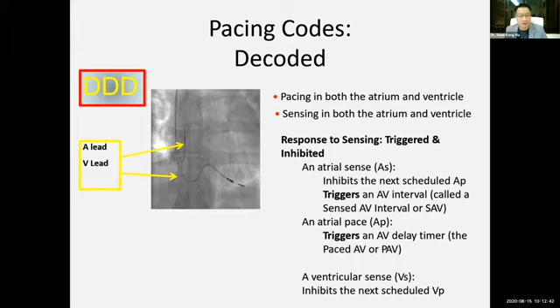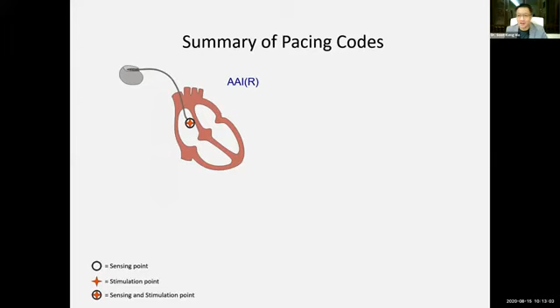Hence, in summary, we have a lot of other pacing codes. You can use the same concept to decode all these different iterations of codes. AAI means pace in the atrium, sense in the atrium, and if you sense an intrinsic activity, you inhibit yourself. VVI, I spoke about earlier on. DDD, I spoke about earlier on, and VDD. Now, VDD is a single lead system, whereby it can sense both the atrium and the ventricle, but only paces the ventricle. This is a very special form of pacemaker.